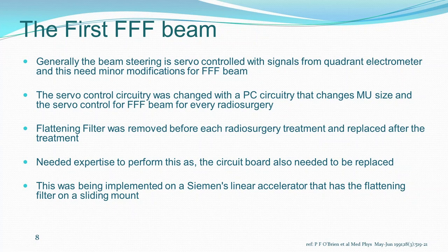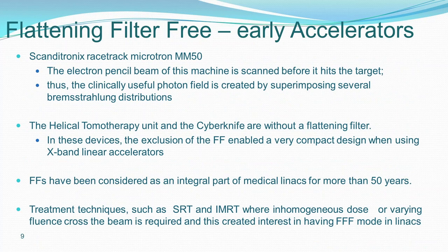The interesting thing was it reduced treatment time, which was beneficial for the patient regarding movement and other issues. They then implemented this in the Siemens linear accelerator, which had a sliding flattening filter, so it was easy — you don't need to remove it; it can slide back and forth. Before actual Triple F beams came into radiotherapy, other accelerators had used Triple F, including the Scanditronix Racetrack Microtron with a scanning beam. Helical tomotherapy and CyberKnife never had a flattening filter, which allowed their compact X-band design.